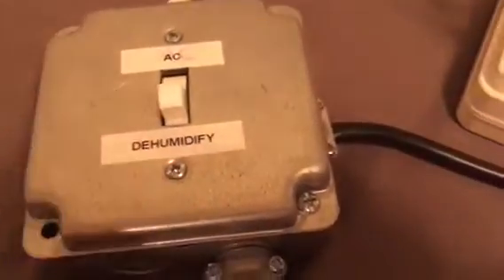This little switch here is very expensive. The humidity switch was fairly cheap. The Leviton switch was expensive because of UL movement or certification. It switches at very high current — people have been using them for generator bypass switches where this is your AC, this is your generator load, and it switches the whole circuit. It looks like a normal switch but it is not — it centers off and handles very high amperage. So this is my solution for now.